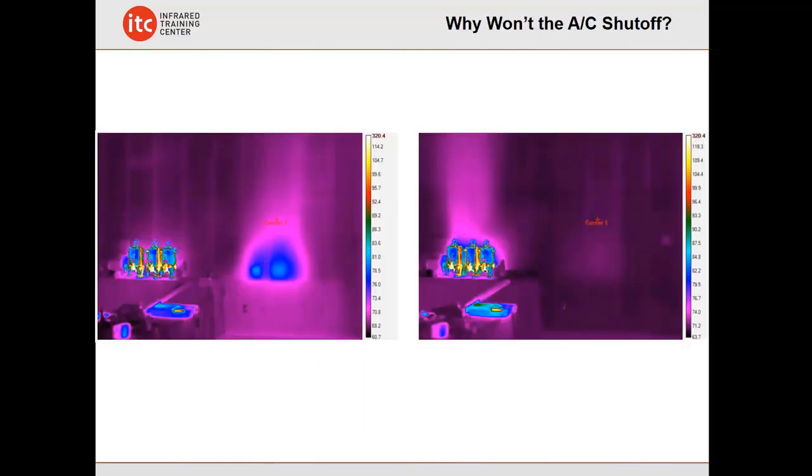We explore our thermal world all the time, all around us. We do training classes in a variety of different locations. This happened to be in a conference room at a hotel out in Las Vegas. A situation where they couldn't get the room to warm up. The air conditioning wouldn't shut off. Turns out the coffee pots were situated underneath the thermostat, causing that thermostat to think the room was much warmer than what it really is. Simply moving them fixed the situation.